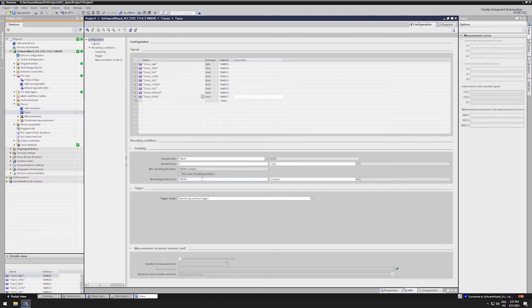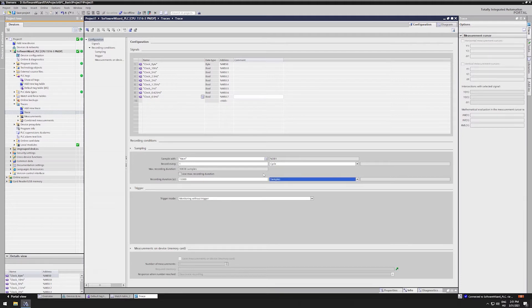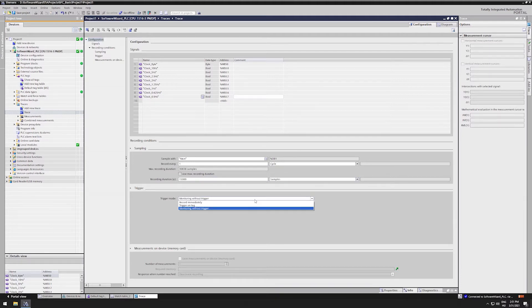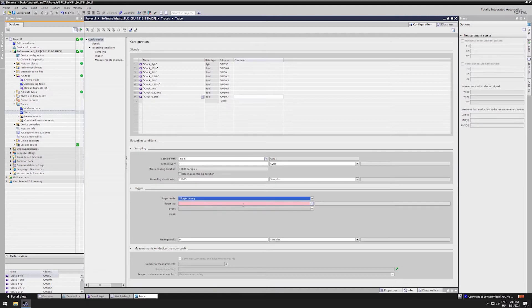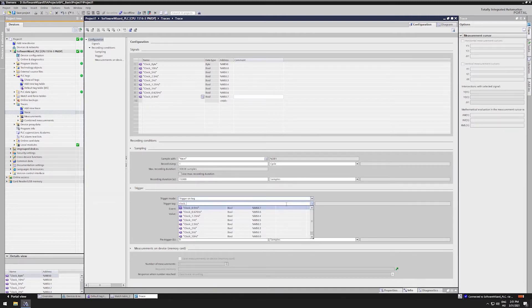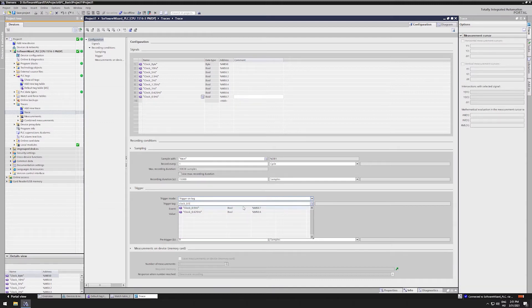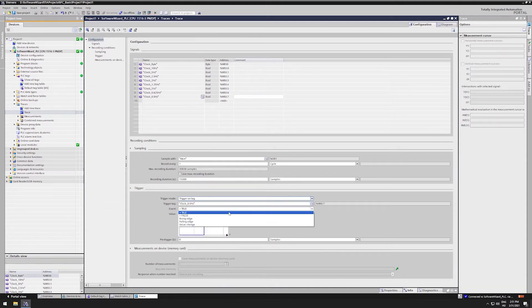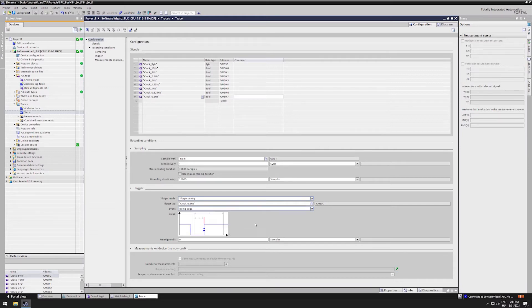In the trigger tag we can choose from three options. One is to record without trigger, in this case the recording starts as soon as we hit recording. The other is to record on trigger, in this case we have to enable our recording and our trigger variable also has to have the desired value to start recording. The third case is when there is no recording, only monitoring. We will use the half a hertz clock signal's rising edge to see the bits alternation synchronously.